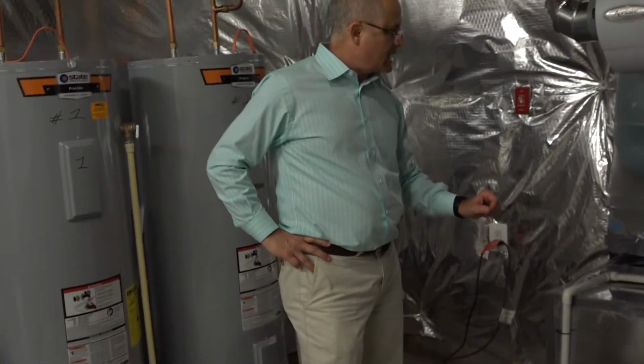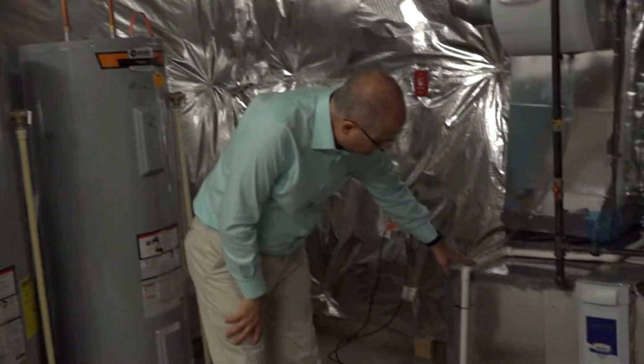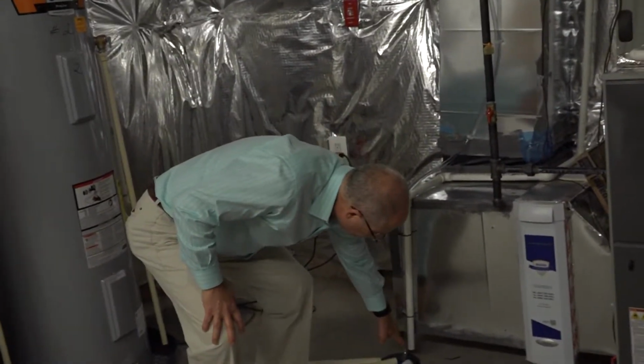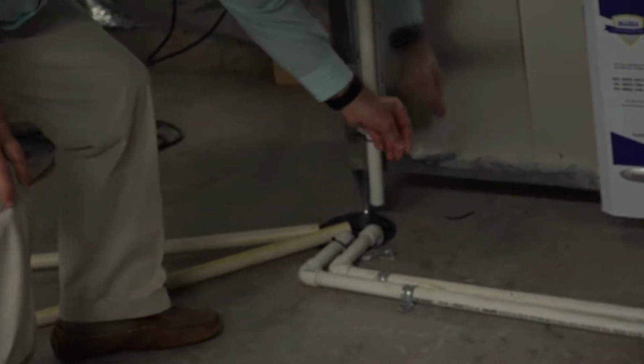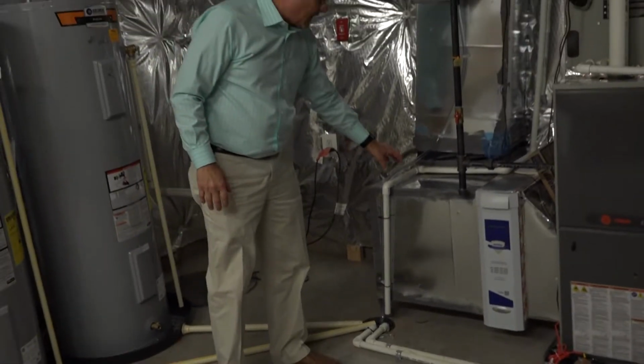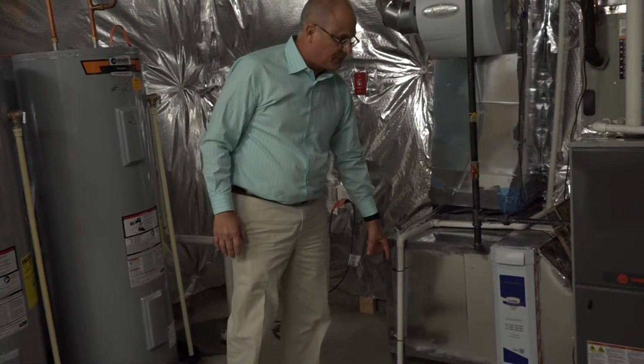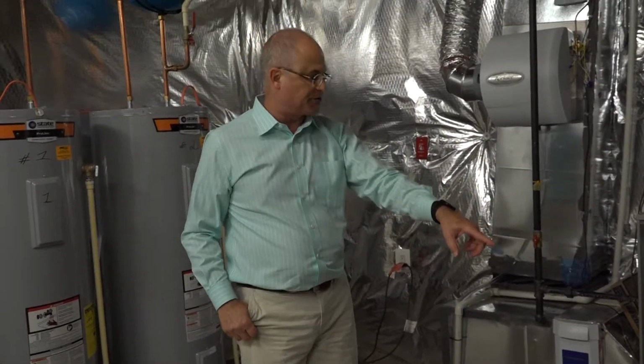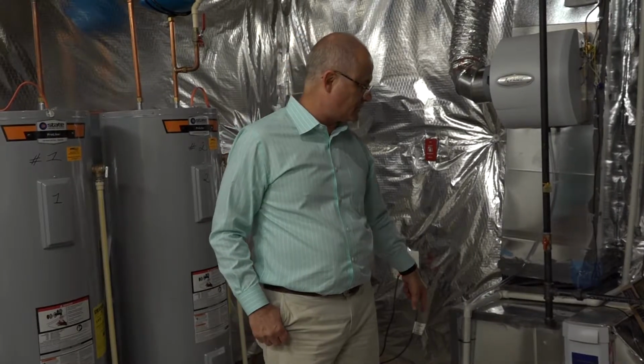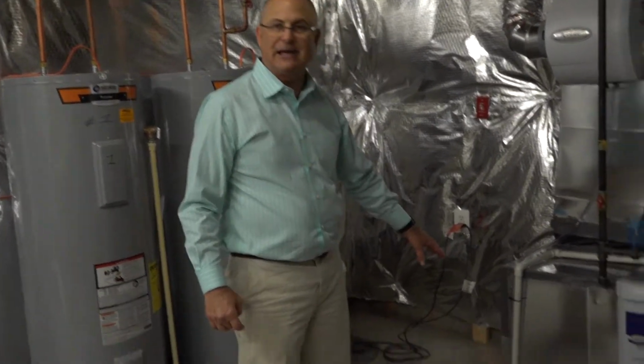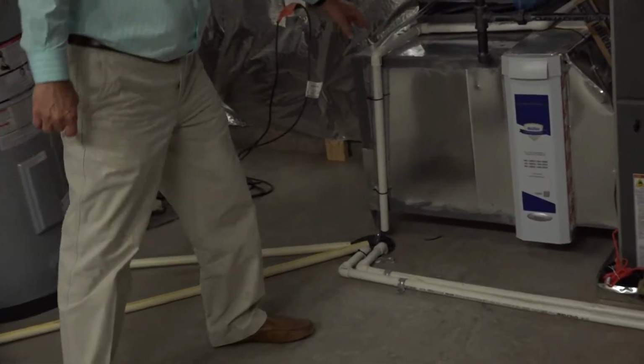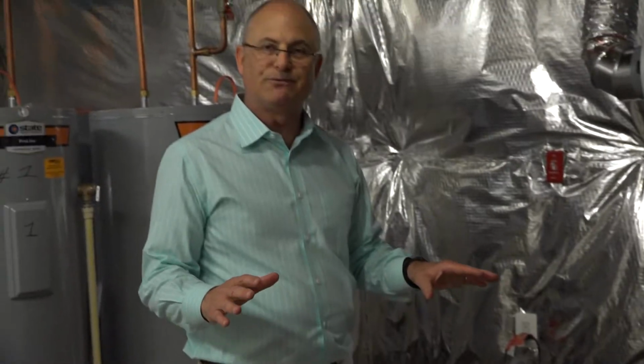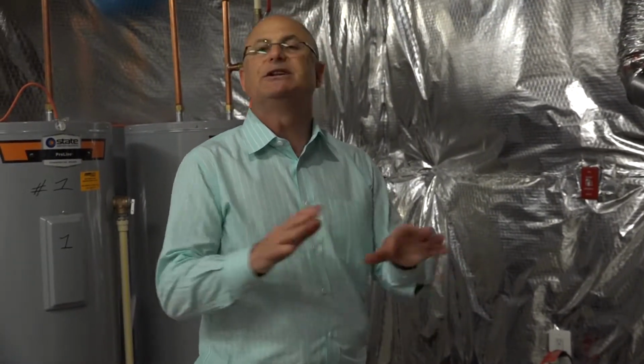The other drains are really condensate drains. In the summertime, condensation is just a natural byproduct of the air conditioning system. In fact, you'll see here off of this system, I don't know if we can zoom in, but you'll actually see the condensation coming from the bottom of the pipe right into the foundation drain. So we've got a condensate drain here going into the foundation drain, and then we have some from other systems, condensate drains draining into the foundation drain. So if you ever see water coming out of a condensate drain in the summer, that is what is supposed to happen.